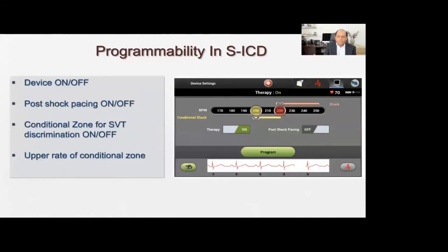The device programming is quite simple. It can be switched on and off. The post-shock pacing can be switched on and off. It is possible to program a conditional zone for SVT discrimination and set the upper limit of the conditional zone, beyond which the device will not apply any SVT algorithms and will deliver a shock directly.